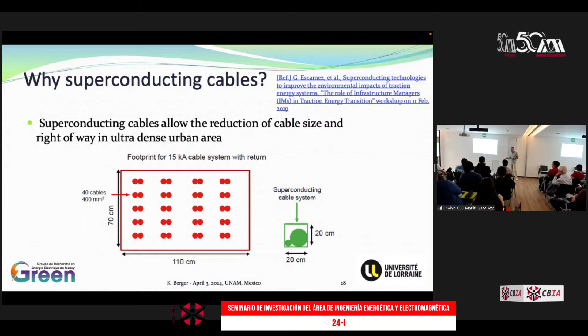So what are the benefits of the superconducting cable? Higher transmission capability at lower voltage, higher transmission capacity at lower diameter. There is no ground heating because it's inside the vacuum cryostat, which means there is no thermal emission from the cable. There is no electromagnetic emission because the magnetic field is shielded inside the envelope. And most of the materials used are 100% recyclable.